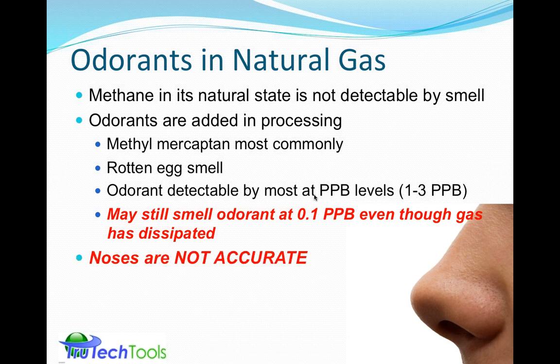And noses are not accurate. They're not calibratable. They're not all the same. They can be affected by an individual's health. So this is sort of the fallback safety position, is to use your nose to smell, but it is not a measurement. It is not to be relied upon as a gas leak detector. If you do smell something, and you're a professional, then you should probably bring out your tool, your concentration detector, your leak detector, and use it to finally narrow down on the leak.